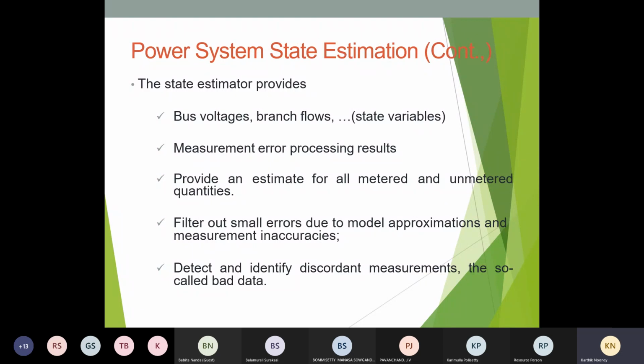So what exactly does the state estimator provide? It provides bus voltages and branch flows, which we will consider in our work as state variables, and measurement error processing results. It provides an estimate for all metered and unmetered quantities, and filters out small errors due to model approximations and measurement inaccuracies. And it can detect and identify discordant measurements, the so-called bad data. This is what the state estimator provides.